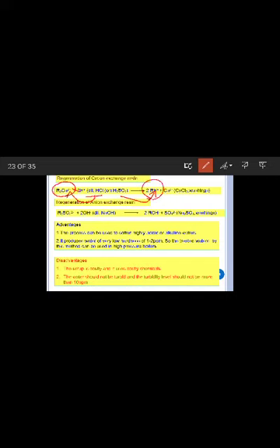And if the anion exchanger is exhausted, we will regenerate it with the help of dilute NaOH. So the resin containing sulfate ions is referred to as the exhausted state. When we add OH- along with that, it will become ROH. So this form is referred to as the regenerated form. So when the resin is exhausted, we will regenerate it with the help of dilute NaOH. So the resin becomes ROH. Now it is ready to proceed with the exchange reaction.